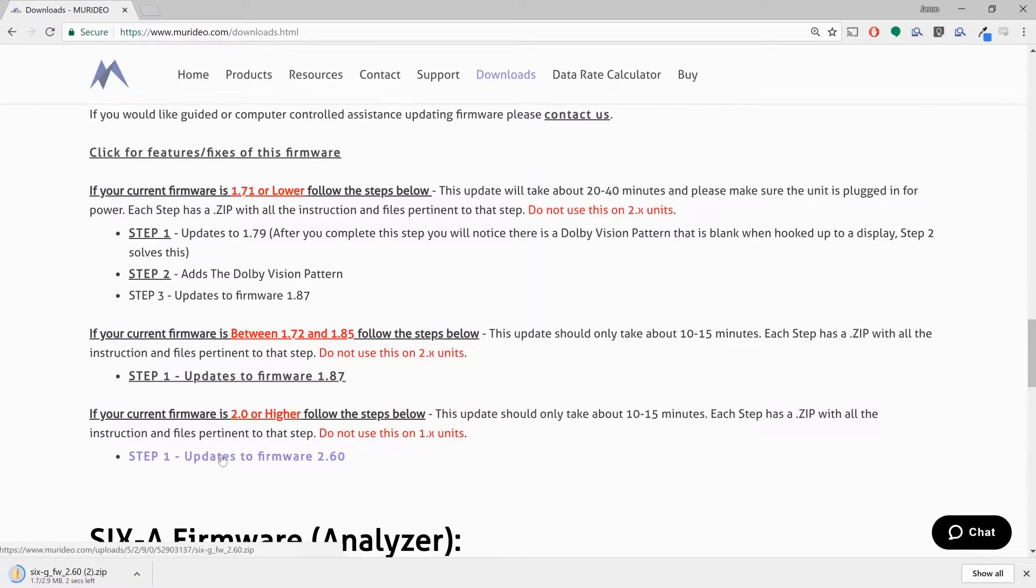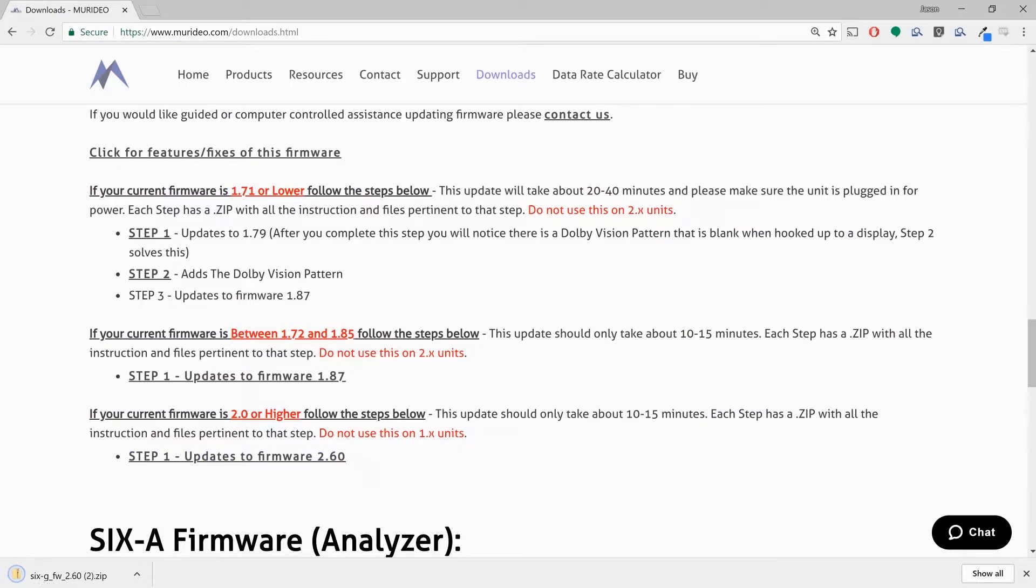While that's downloading, I do want to point out something very important. If you try to put 1.anything firmware onto a 2.0 machine, you could brick the machine. Same thing vice versa. If you have a 2.0 machine and you try to load 1.0 firmware onto it, again, you will brick it and it will have to come in for service. So be very, very careful to make sure that you're downloading the right firmware version for your specific generator.